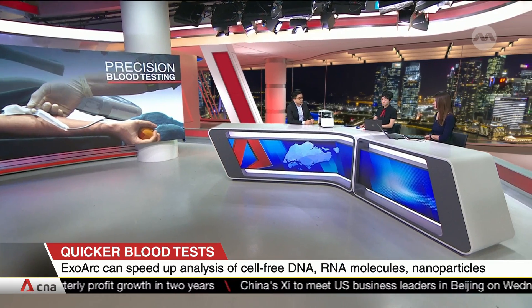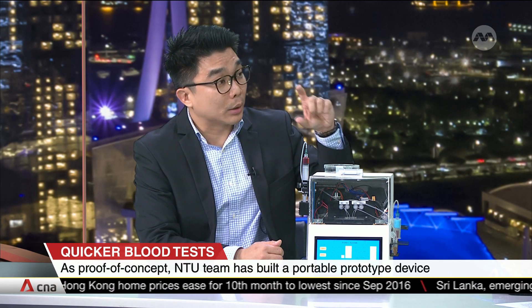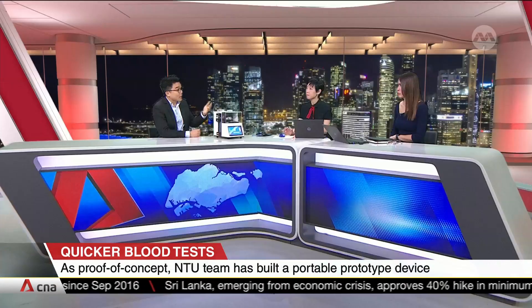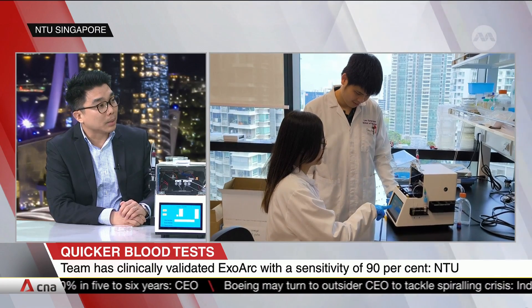For the chip part, because we separate out the cells and blood is pumped in at very high speed, the key feature of this device is that it is very gentle in terms of sorting out the plasma. For centrifugation, you spin the blood for about 20 minutes and the cells settle down because they are denser, then you collect the yellow liquid on top as the plasma. This process is not very efficient and typically has to be repeated twice by a technician, involving a lot of manual steps, making it time-consuming and highly dependent on the skill of the operator. This is why we try to automate and standardize the whole plasma isolation process.